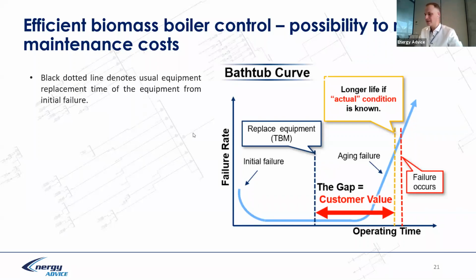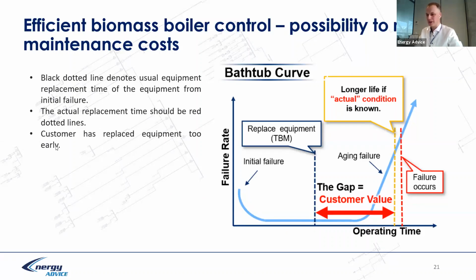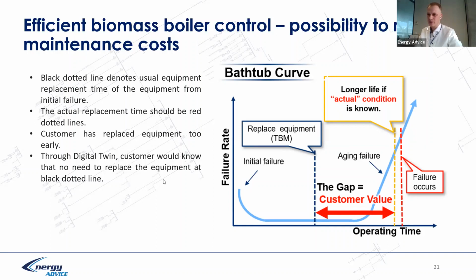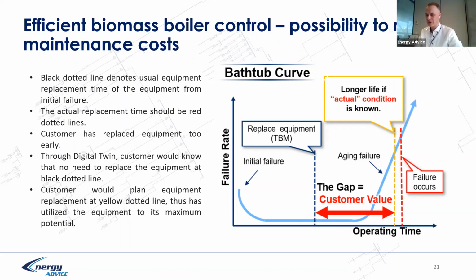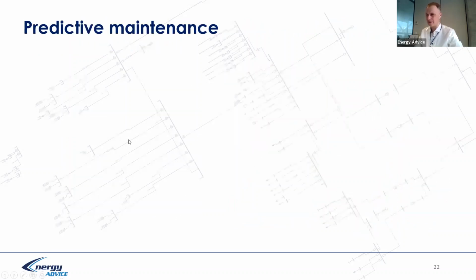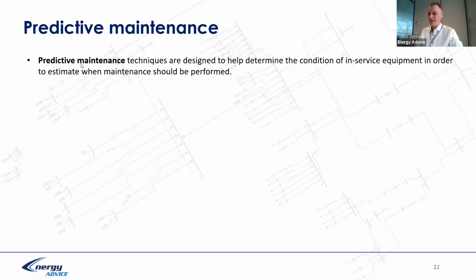So black dotted line denotes usual equipment replacement time of equipment from initial failure or after maintenance. If a boiler is operating, for example, 2, 3, 4, 5 years, the actual replacement time should be red dot line probably. Customer has replaced equipment too early, and through digital twin, customer would know that no need to replace equipment at the black dotted line. Okay, and customer would plan equipment replacement at yellow dotted line, which has utilized the equipment to its maximum potential. So through this, we can save part money for the maintenance. Predictive maintenance, in general, it is a technique designed to help determine a condition of in-service equipment in order to estimate when maintenance should be performed.